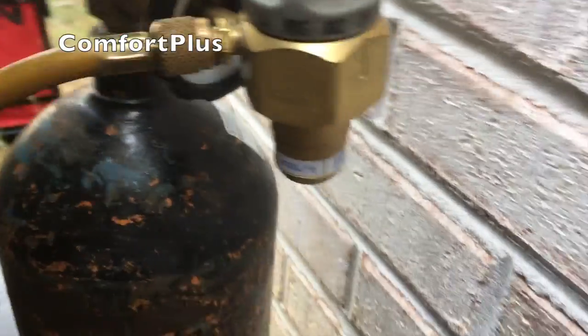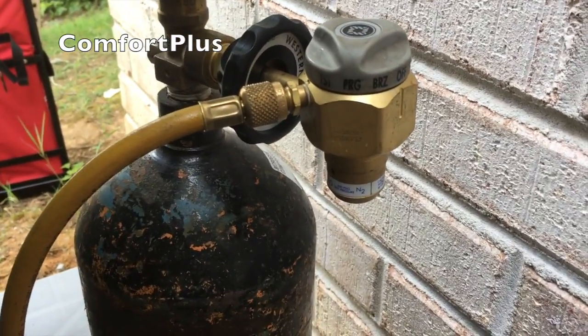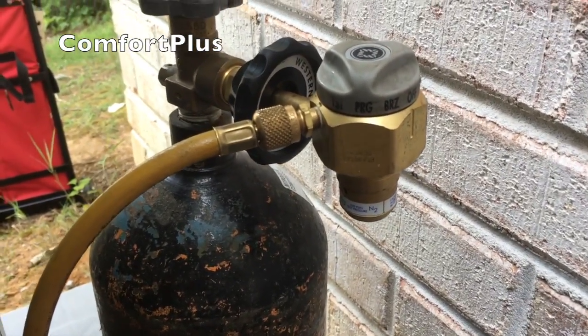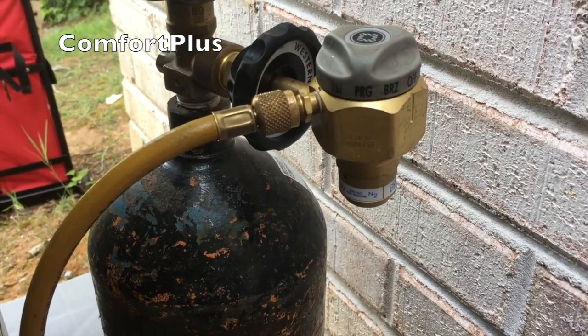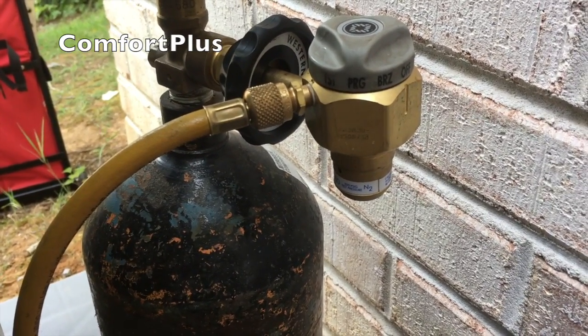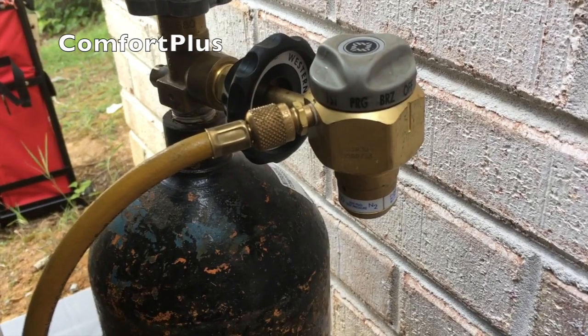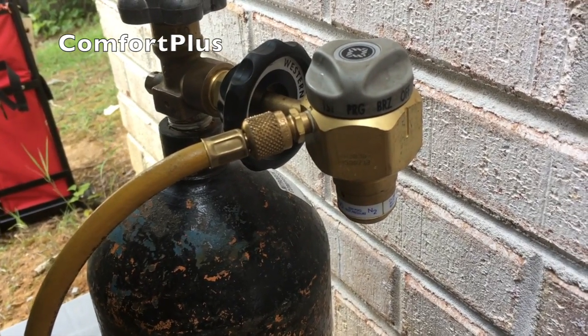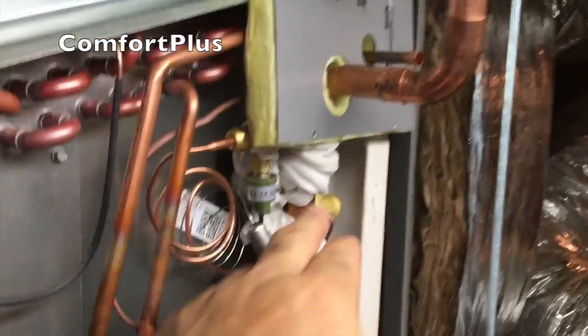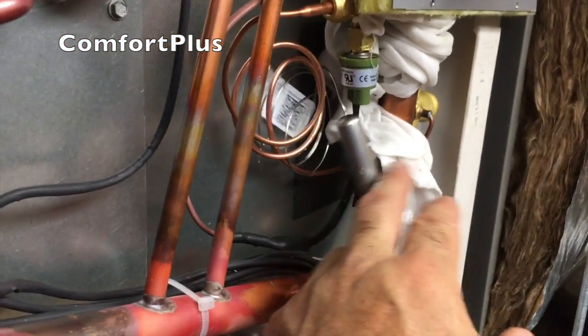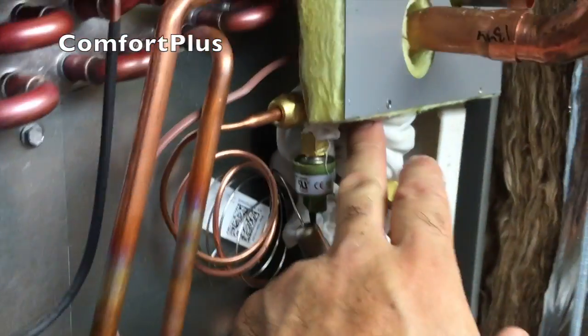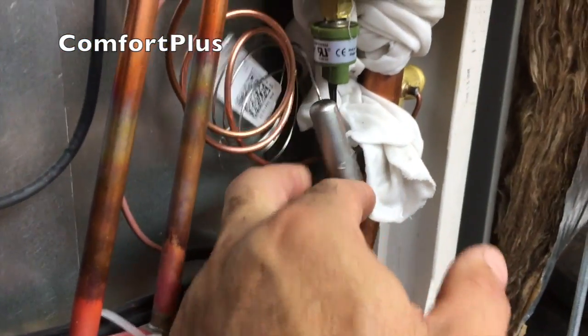Just set it on braze and it flows the perfect amount. I usually turn it on to purge or even test if it's an open line on the other end, just to get the line full of nitrogen to start with, and then leave it on braze, and it just flows a little bit through the whole time you're working. Okay, underneath, always remove the bulb, even though I wrap everything with a wet rag because I'm chicken.